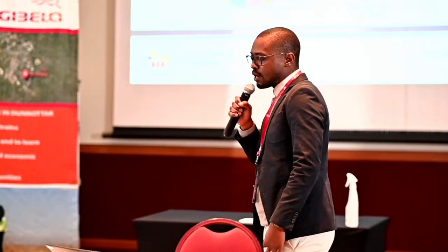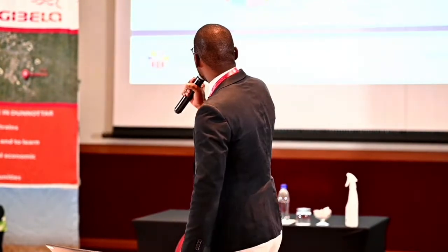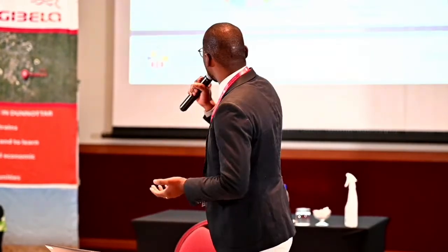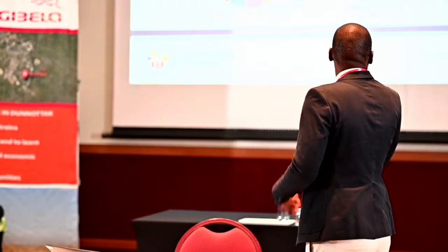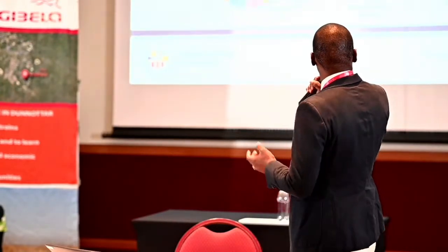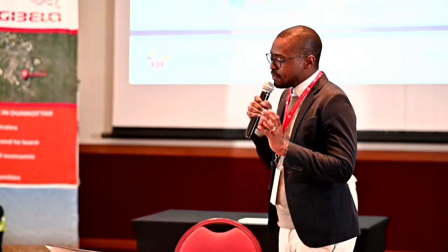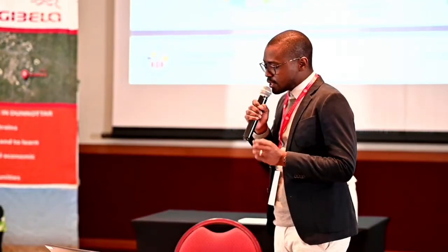Further on, with the tool, I was also able to identify a lot of factors in terms of frequency of interruptions and also equipment failure rate. As you can see, I can identify that transformers are the ones that are more troublesome, and on that, maintenance can be specific to address and minimize faults that are occurring a lot on transformers.